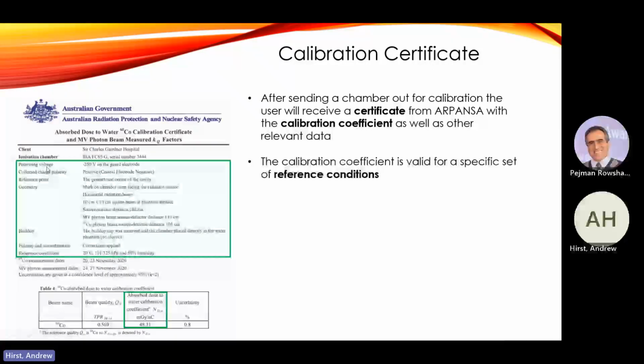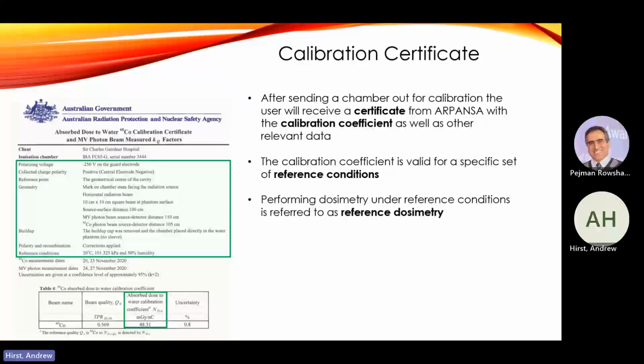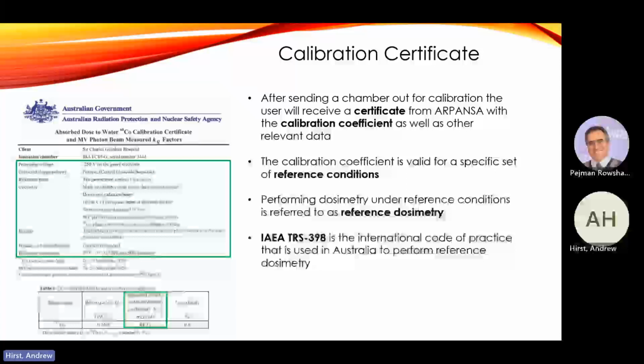The polarizing voltage, the reference point that they took the measurement at, the geometry of the setup, field size, the depth, the energy, the temperature, the pressure, all these things are important. And that coefficient only applies to those conditions. Any departure from those conditions you have to correct for. When we perform dosimetry under these reference conditions, we call it reference dosimetry. So it's another terminology thing.